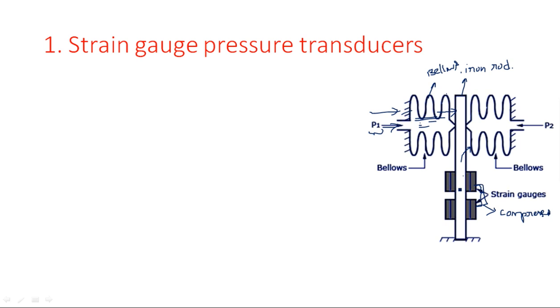Because the movement is in the right-hand direction, the right-side gauges are compressed, and the two gauges on the other side are getting elongated. Because of this compression and elongation, the resistance of the strain gauges will vary. When we connect these strain gauges in a bridge — used to measure resistance change — the electrical property can be calculated, which is proportional to the applied pressure.